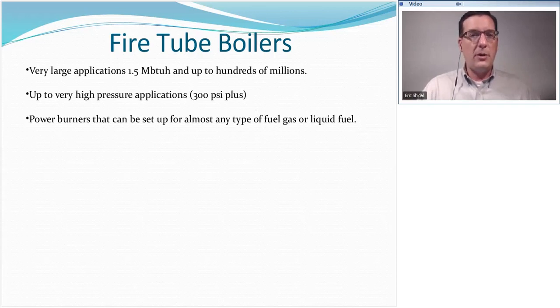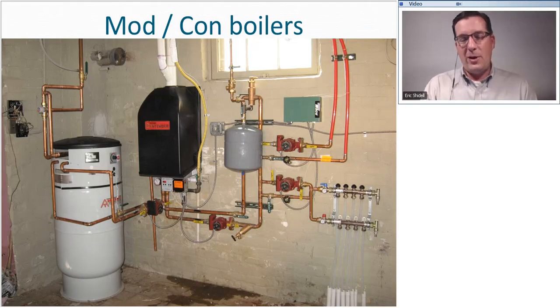So the next boiler we're going to talk about is called the ModCon boiler. This is another one of my favorites. This is the modern invention. Mod, in this case, does not stand for modern. It stands for modulating. Modulating/condensing boilers. If you're familiar with high efficiency furnaces that have AFUE ratings above 90%, condensing gas furnaces, this is the boiler version of that, but it's even more deluxe and even more high tech.